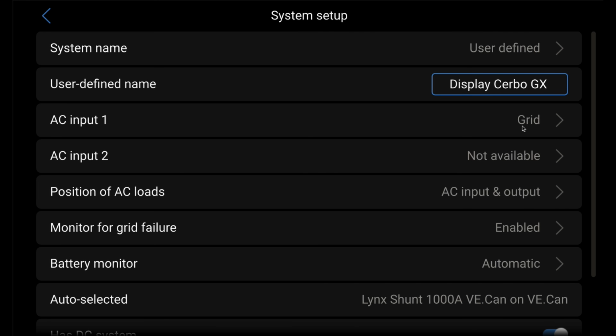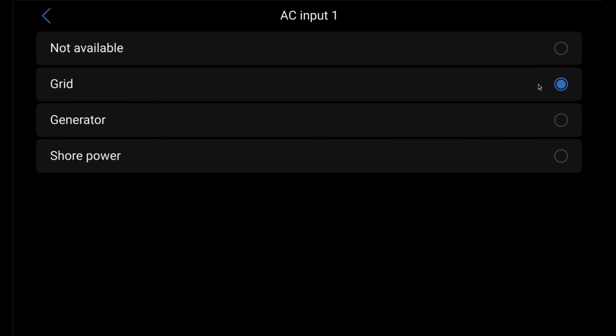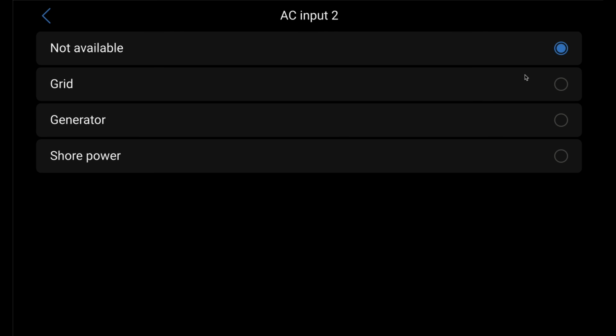In this case, we're running a multi-plus inverter, which only has a single AC input, so we click on that and tell the system what power is coming into that input, in this case a grid connection. We can also select generator or a shore power connection as a more generic option. If you have a Quattro inverter, you'd also come in here and define what AC Input 2's source is.